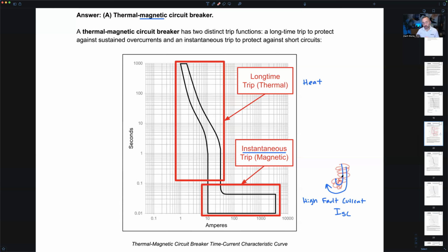So at all times, when that breaker is closed under normal, non-overcurrent conditions, you've got a curve in the shape, and maybe here's a contact right here. This is an oversimplification, by the way, but you've got a shape built into the metal that makes the electrical contacts want to open from the magnetic field created by the current traveling through it. They build these breakers with very specific ratings such that this one is going to trip as low as 10 amps. At 10 amps, that magnetic field is just strong enough to open the contacts, trip the breaker, de-energize the circuit. That's for high fault current. That's the magnetic trip function of a thermal magnetic breaker.